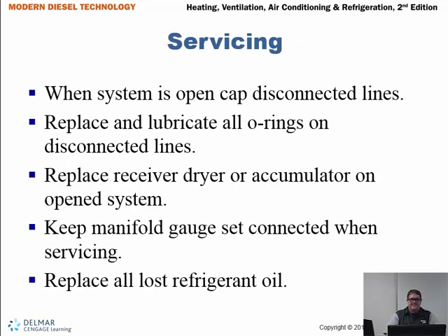So as we're servicing this, we need to cap the lines. Replace and lubricate all O-rings on all disconnected lines. Replace the receiver dryer or accumulator on open systems. Keep the manifold gauge set connected when servicing, and replace all lost refrigerant oil.